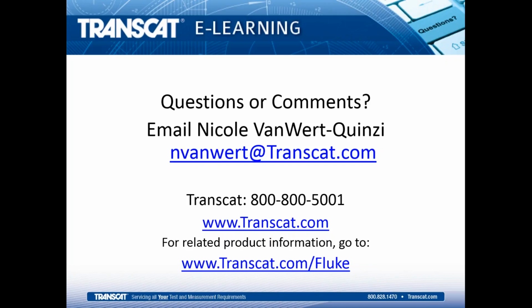So I'm not sure I quite get this question. So we've got a Fluke 52, we've got a dry block. There's differences in the resolution between the two. Is that what he was talking about? Yeah, the 52 reads only to the 0.1, but the dry block reads to the 0.001.